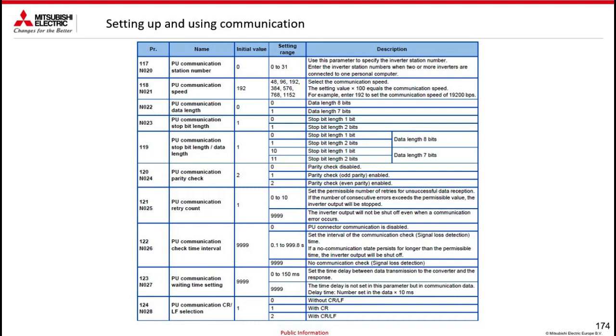You just need to know that the inverters already have serial communication on board, so it will allow you to manage it completely, as if you were managing it from the outside. You can give frequency references, run commands, you can change parameters, read the monitor, reset the inverter, clear the inverter. You can do whatever you want, both in terms of the data and in terms of the serial communication. You can also manage the Mitsubishi protocol, like the slide that I am running very fast, and also the Modbus RTU, which is also very simple. I already have some predefined registers, and I just need to point to them correctly, and the game is done.